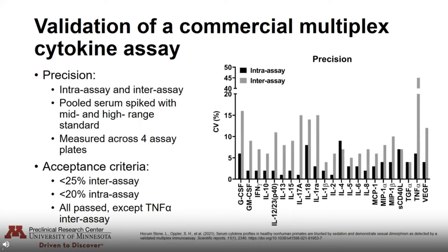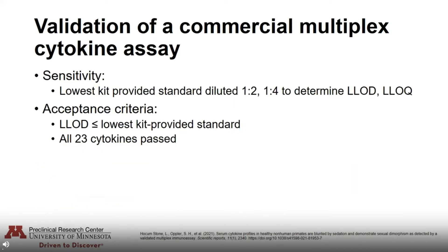Next we looked at precision — both intra- and inter-assay precision. To do this, we pooled serum spiked with both mid- and high-range standards and measured these across four assay plates. Our acceptance criteria was CVs below 25 percent for inter-assay precision and below 20 percent for intra-assay precision. All analytes passed except for TNF-alpha inter-assay precision.